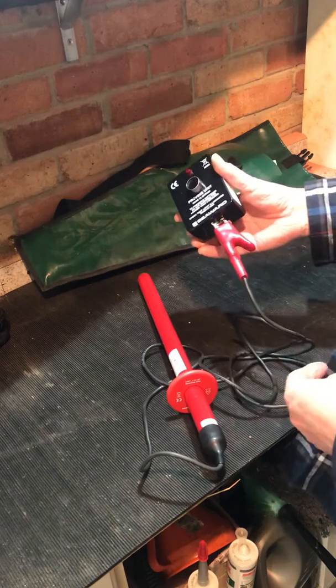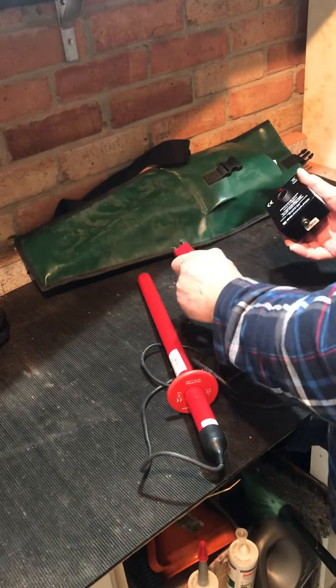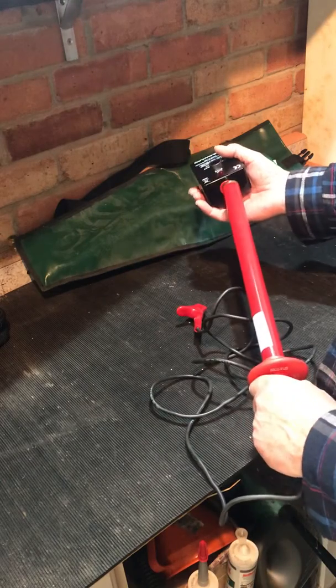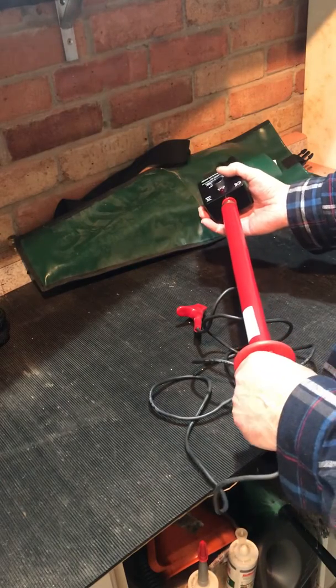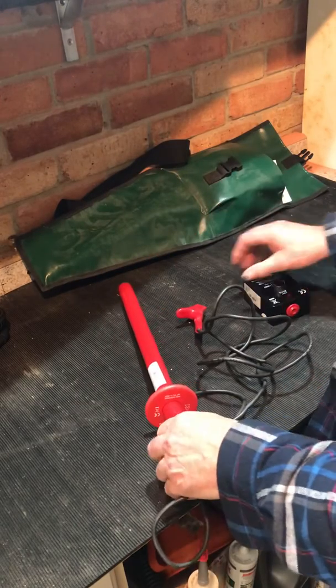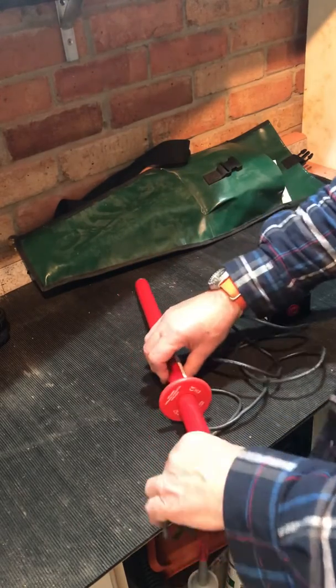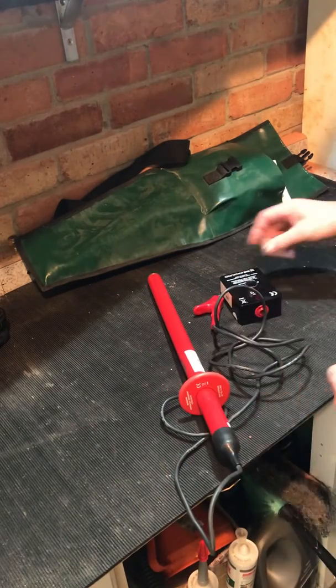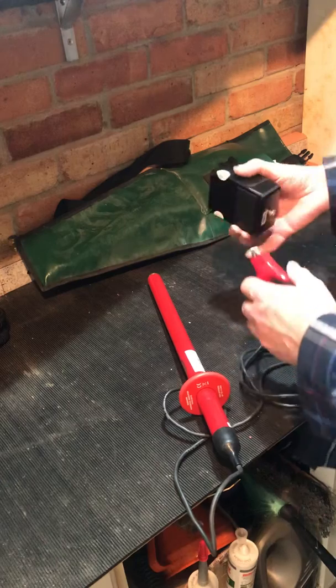Connect the clamp to the chassis, proving unit to the chassis, probe to the chassis, and prove it, measure, prove. HV again — requires permits, safe systems of work, and competency, or it will blow you apart.